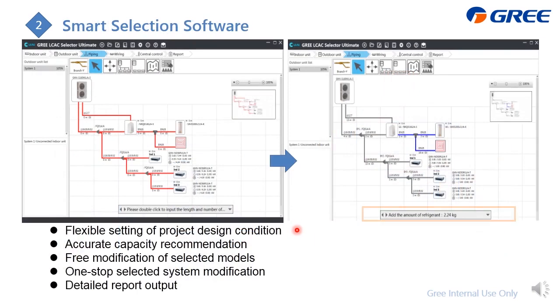Also, on the GMV selector, we also have the GMV Home series selection. Just input your information, so you can also get the water tank and also floor coil. This is the hydro box. After you input the information of the pipeline, the system can automatically calculate how much refrigerant you need to additionally charge. And also you can check whether your combination is okay or not. And for this part, it's completely the same as the regular heat pump system.